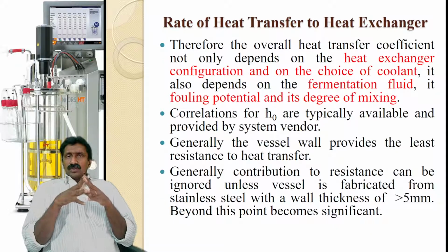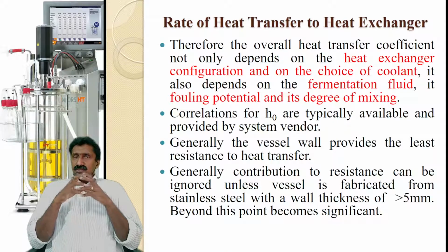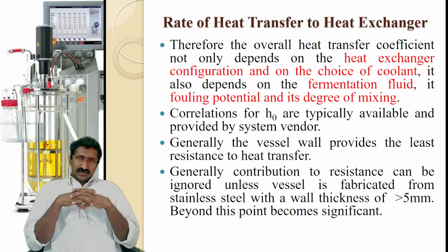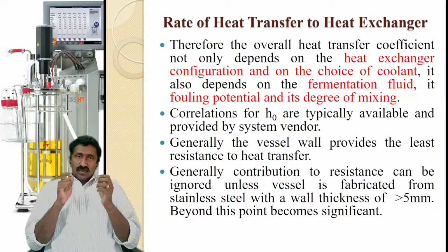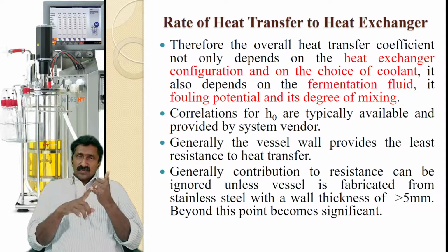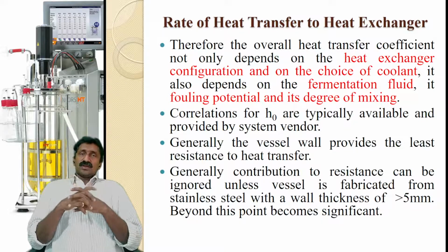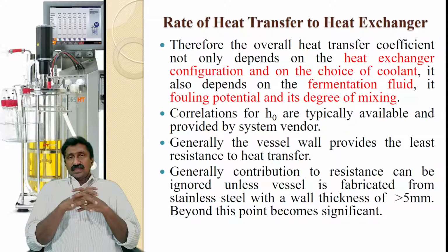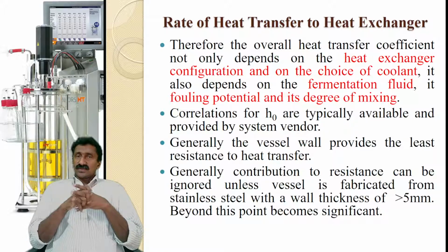So therefore, the overall heat transfer coefficient is not only dependent on the heat exchanger configuration and the choice of the coolant. It also depends on the fermentation fluid and fouling potential and even the degree of mixing. So various parameters are involved in determining the overall heat transfer efficiency.